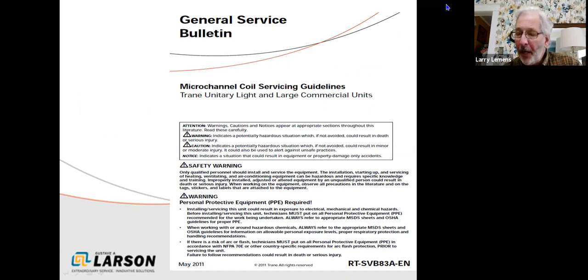This is another one. If you guys want this particular bulletin, let me know. It's microchannel coil servicing guidelines. It's probably another good one to have if you're doing service in the field. I'm not going to spend a lot of time on it, but it is available. Basically, if you're going to use any coil cleaners, they want you to use a pH neutral balance on the coil cleaner, like Evap Green or something chemically stable or at a pH of 7.5 to 8 usually works for you if you're going to do any kind of chemical cleaning.